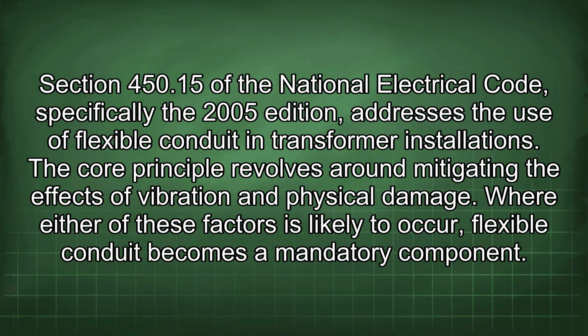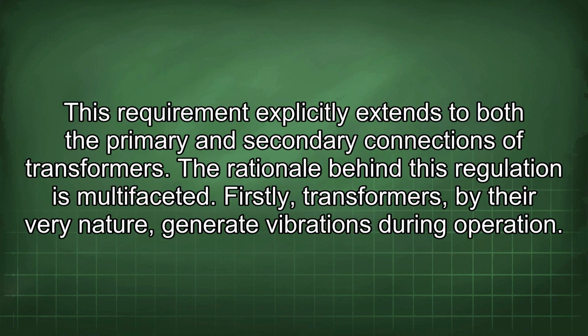Section 450.15 of the National Electrical Code, specifically the 2005 edition, addresses the use of flexible conduit in transformer installations. The core principle revolves around mitigating the effects of vibration and physical damage. Where either of these factors is likely to occur, flexible conduit becomes a mandatory component. This requirement explicitly extends to both the primary and secondary connections of transformers. The rationale behind this regulation is multifaceted.